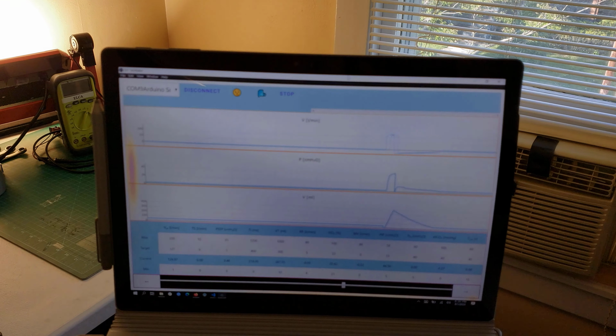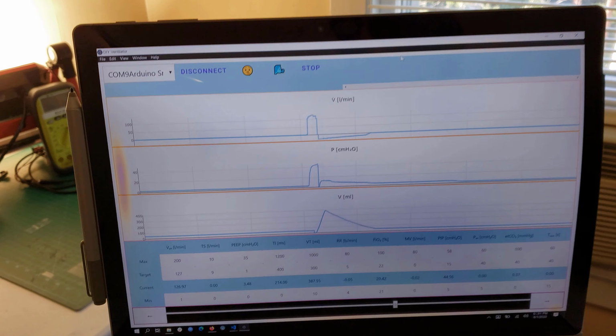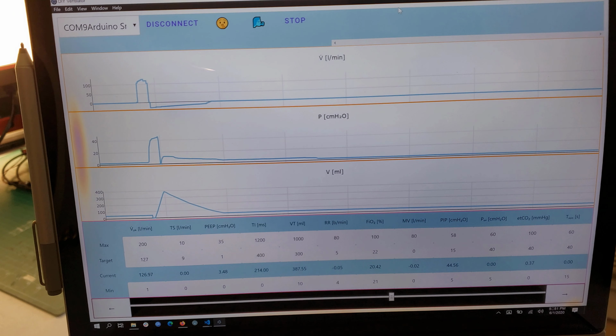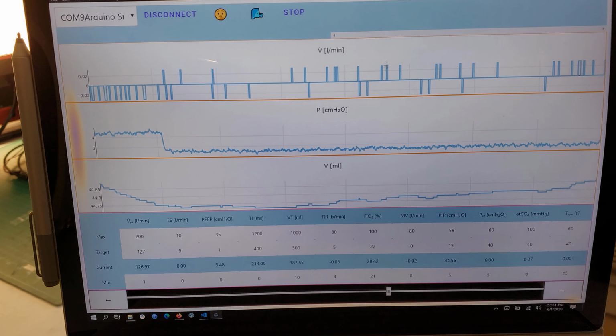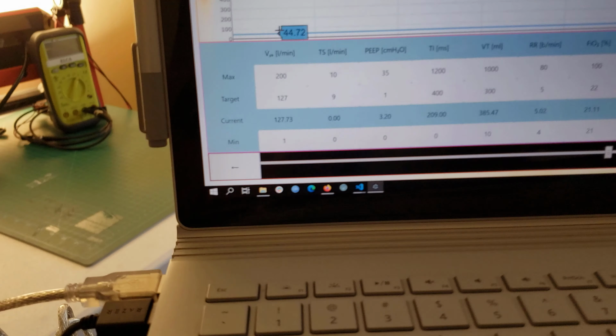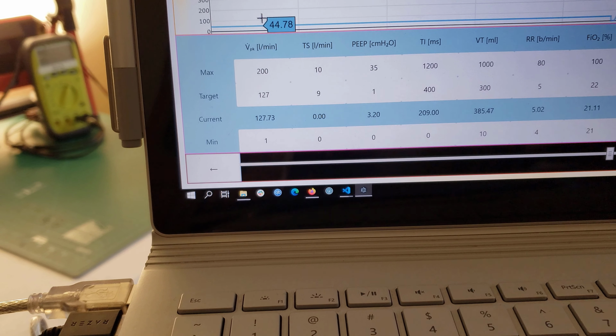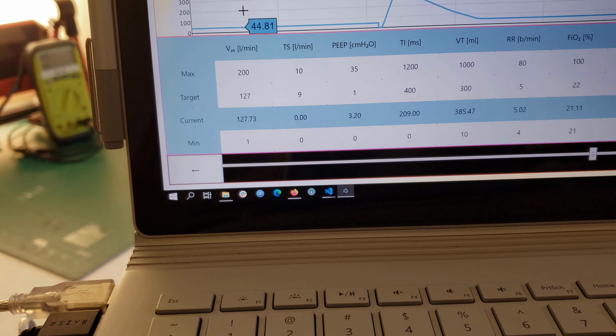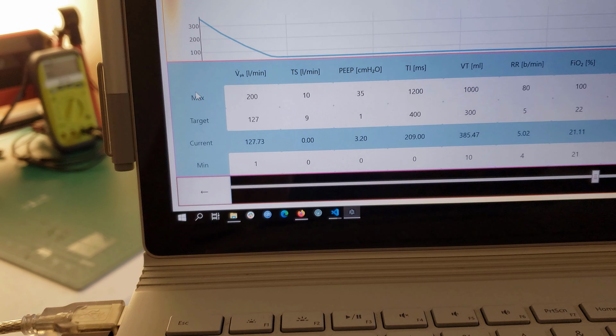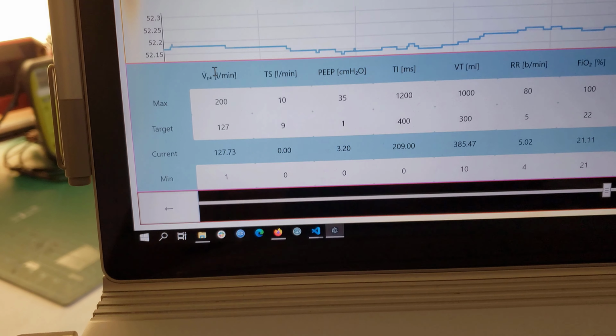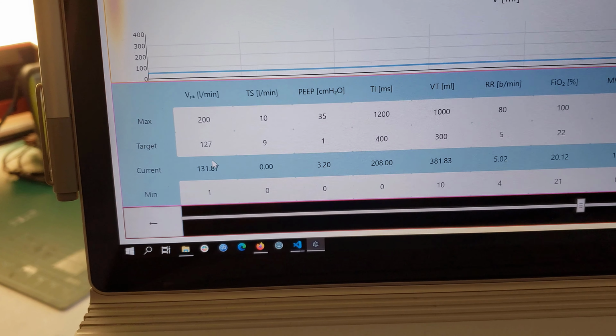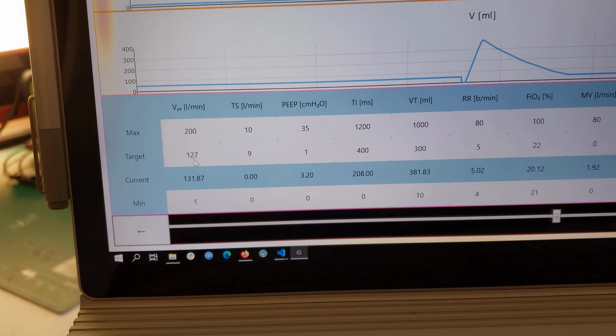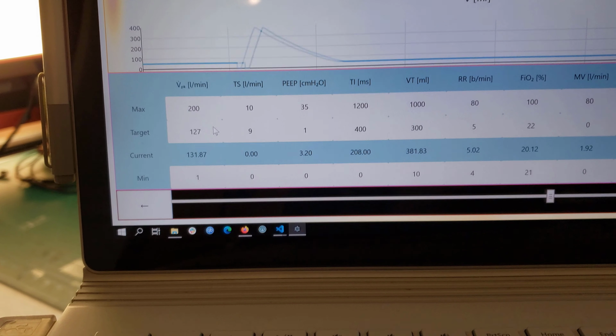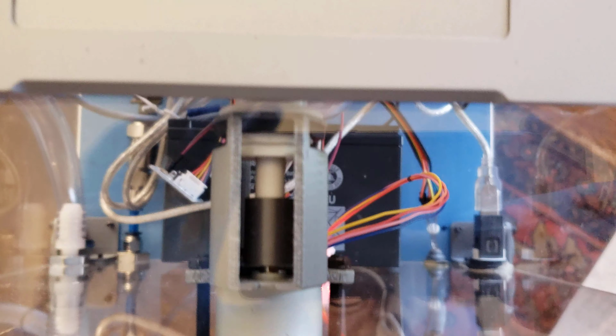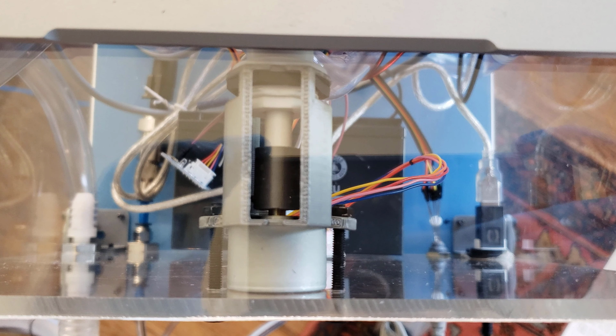So here's the volume controlled ventilation mode. Starting with the plots, we have flow in liters per minute, pressure in centimeters H2O, volume in milliliters, and on the bottom we have all of our set targets and current fields displayed, and the alarm maxes and alarm mins. Starting from left to right, we have peak flow, and right now this is set to 127. We can set that all the way down to 60 liters per minute, and this PFC that we built with a stepper would rotate to hit the target peak flow.